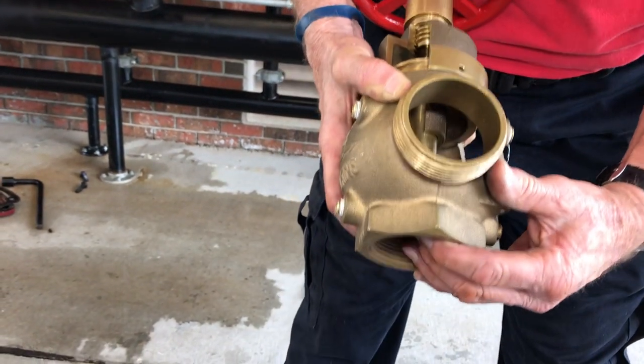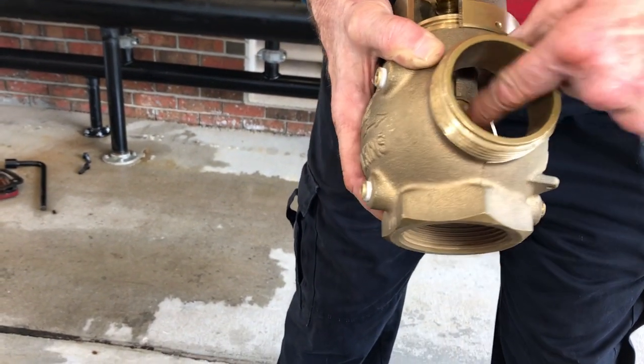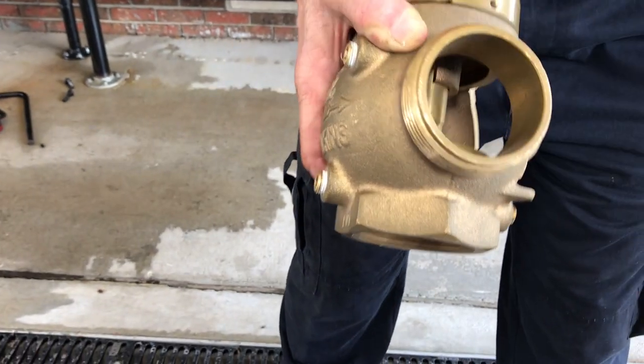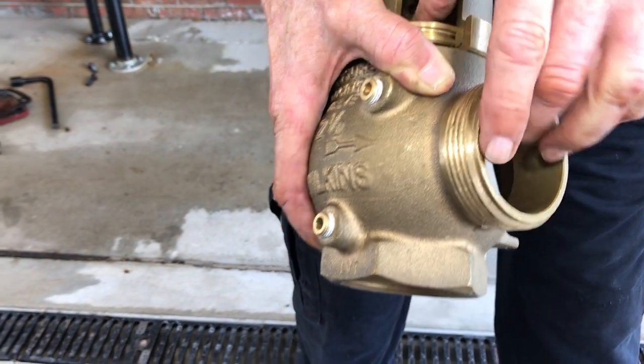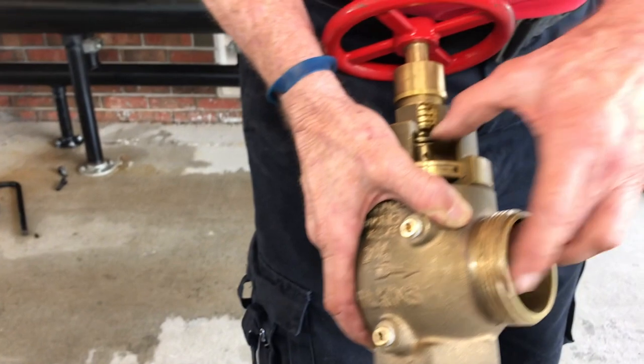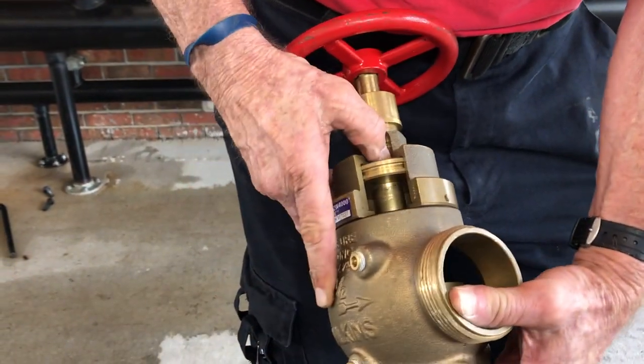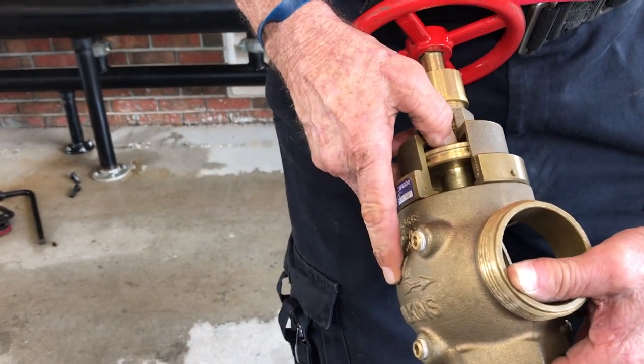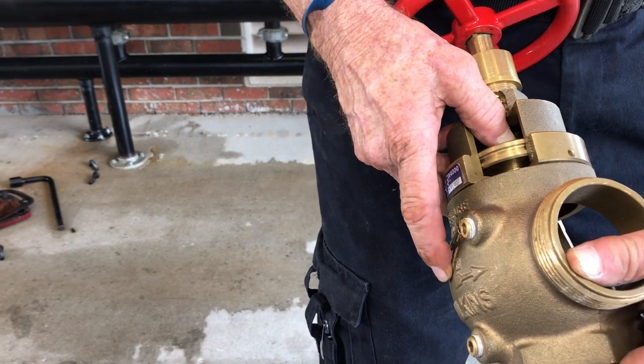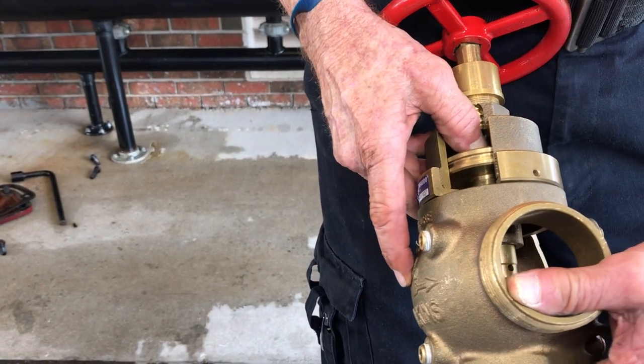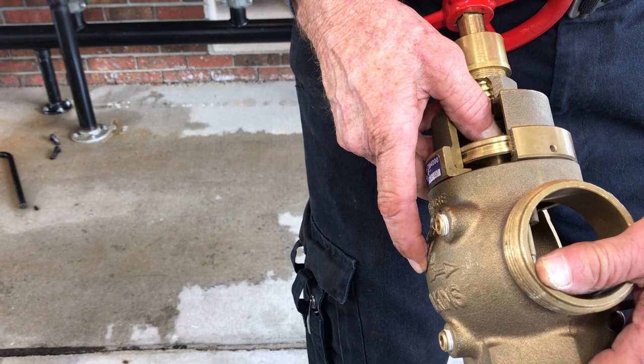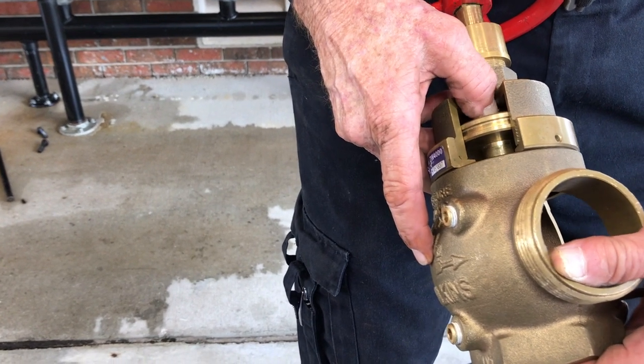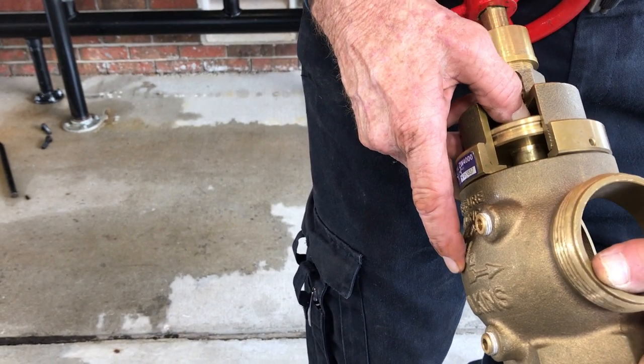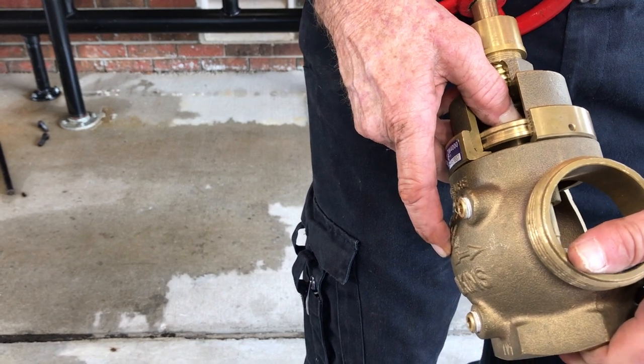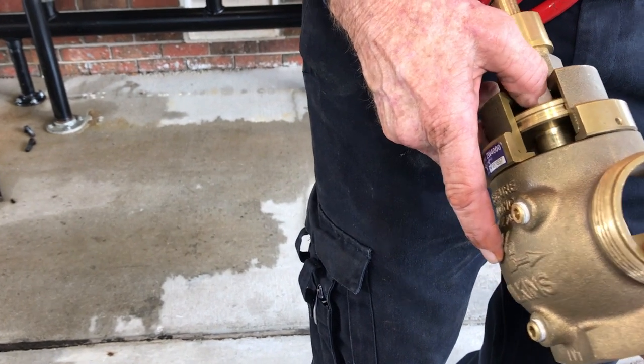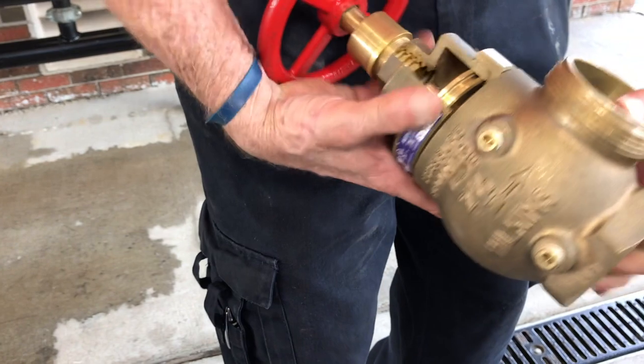Pressure drops. There's a waterway here. It allows water to flow up and fill this chamber. Water in this chamber acts upon this piston, opens, closes, or throttles this valve and controls the pressure in both static and in flow. How can you tell the difference between a pressure reducing valve and a conventional?